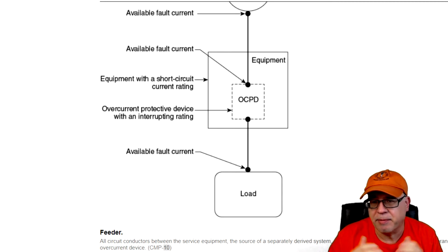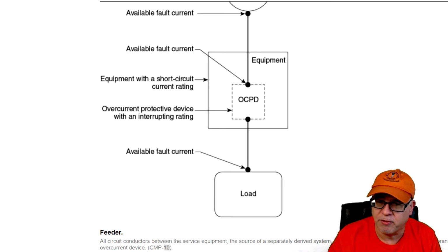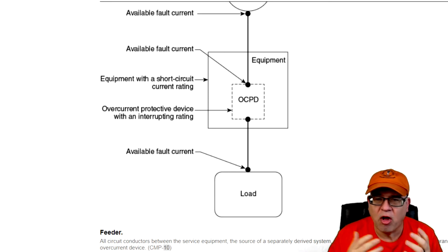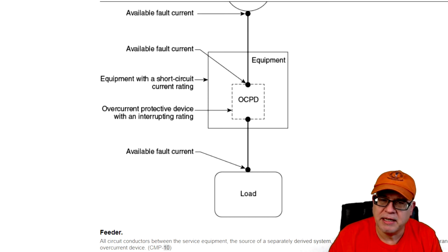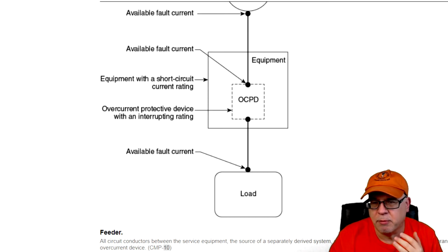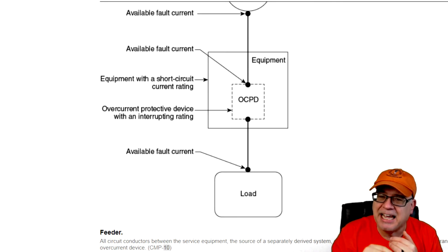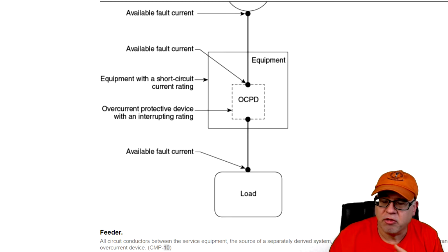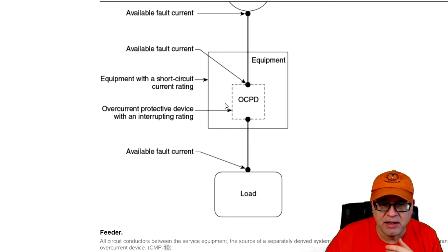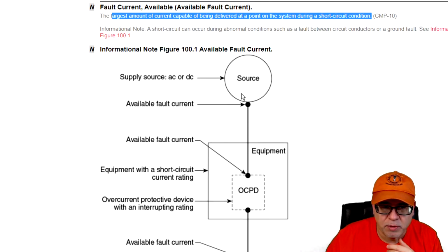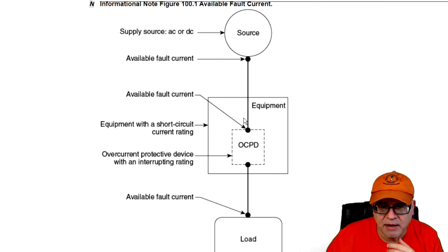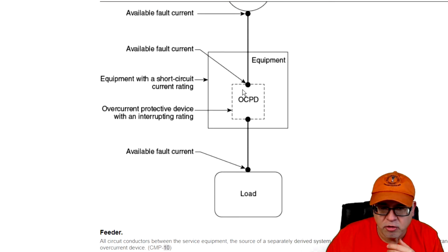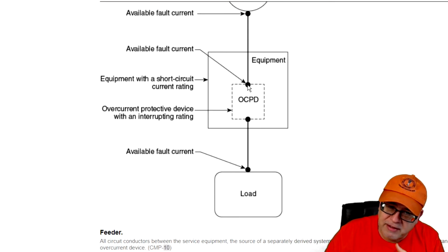Okay, and that is typically going to be equal to or greater than the available fault current. So you have all these things that come into play when you're dealing in this type of circuit, but just important to know that the available fault current is the maximum amount of current during a short circuit condition at a given point in the system.